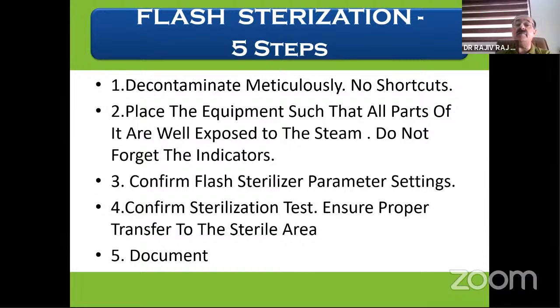so that when the process is finished, you check the indicator that you have achieved sterilization, that the appropriate temperature has changed the color of the indicator. After confirming the flash sterilization parameter settings, one must confirm the sterilizing test, ensure proper transfer to the sterile area. So from the flash autoclave into the operating field, this carriage also should be done with gown, gloves, and it should not be taken lightly. Finally, document everything that you have done, and especially the parameters and the indicators.